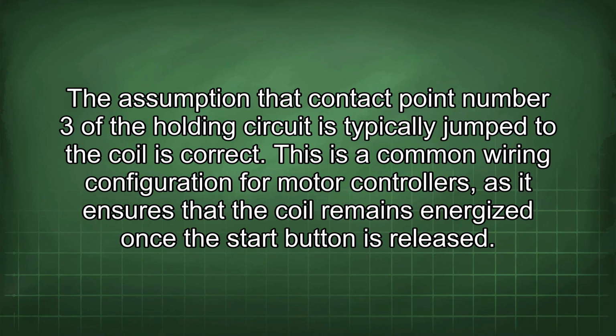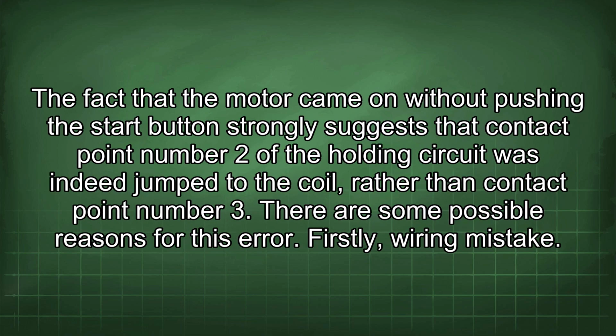The assumption that contact point number 3 of the holding circuit is typically jumped to the coil is correct. This is a common wiring configuration for motor controllers, as it ensures that the coil remains energized once the start button is released. The fact that the motor came on without pushing the start button strongly suggests that contact point number 2 of the holding circuit was indeed jumped to the coil, rather than contact point number 3. There are some possible reasons for this error.